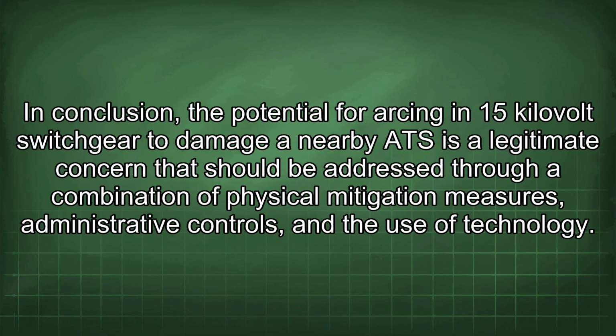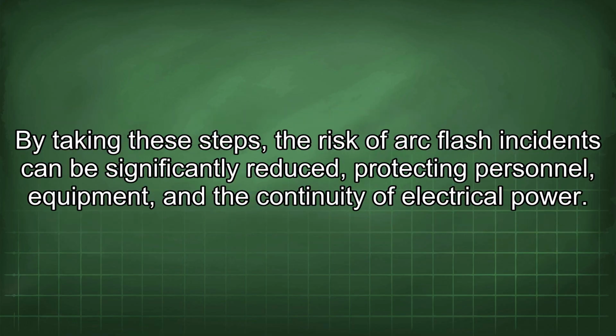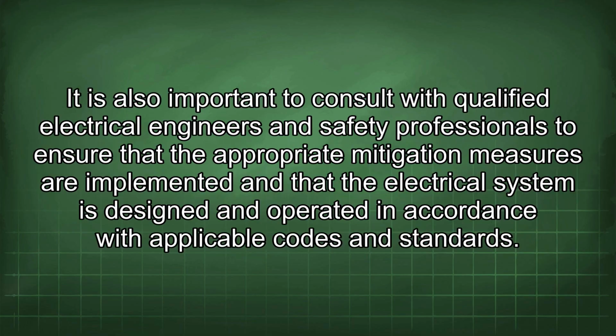In conclusion, the potential for arcing in 15 kV switchgear to damage a nearby ATS is a legitimate concern that should be addressed through a combination of physical mitigation measures, administrative controls, and the use of technology. By taking these steps, the risk of arc flash incidents can be significantly reduced, protecting personnel, equipment, and the continuity of electrical power. It is also important to consult with qualified electrical engineers and safety professionals to ensure that the appropriate mitigation measures are implemented and that the electrical system is designed and operated in accordance with applicable codes and standards.